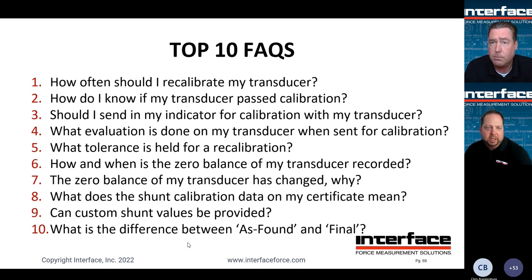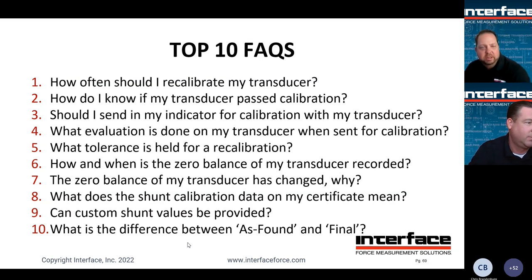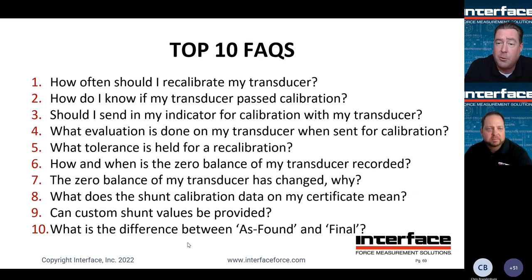So I got a follow-up question to that, Elliot. Can I use a load cell if the zero balance has changed? That's a good question. And typically speaking, our threshold is 10% of rated output. So if we see a load cell that's shifted more than 10%, our standard recommendation is to replace the load cell. There's two common factors here. Number one, if it's shifted that much, that means that the load cell flexure or the spring element is yielded, and there potentially could be a safety issue, right?